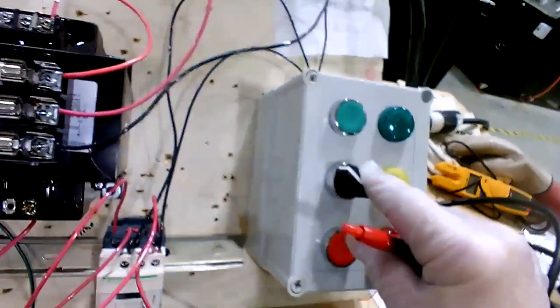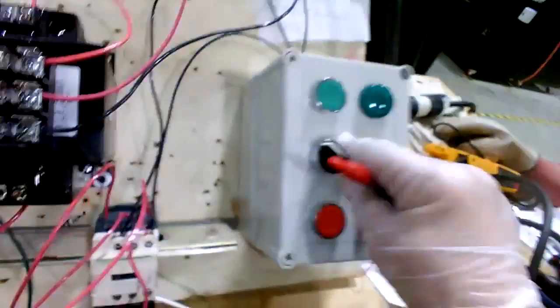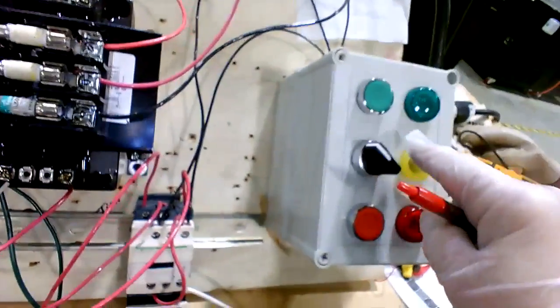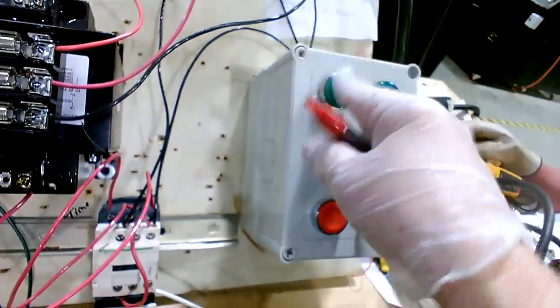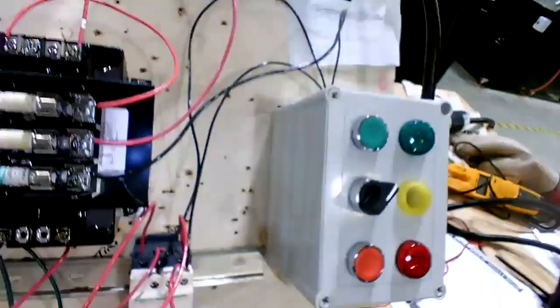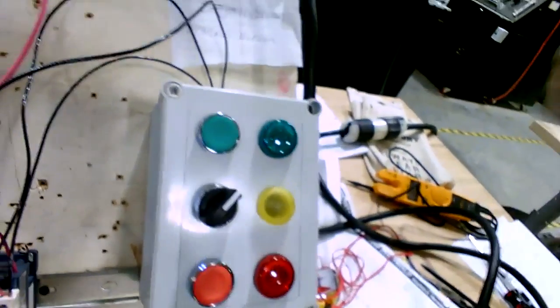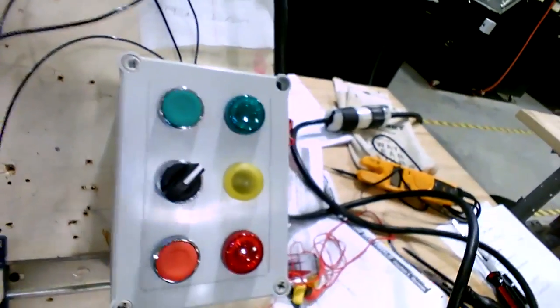Got it? And then the jog switch. We want it so that when you're to the right, to the left, if you're in run mode, when you hit this, it's going to run. When you're in jog mode, we want that to be momentary. When you press it, it runs; you let go, it quits. We want it so that you can just bump the button in jog mode. So the way that works is like this. The way the jog switch works is like this.